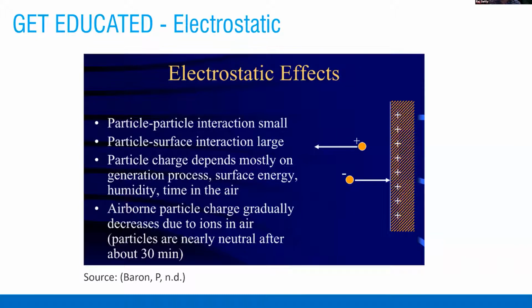Electrostatic, otherwise known as corona discharge or electrostatic precipitators, is a technology that in essence charges the particles. And you'll have a couple different ways where it charges the particles. Either the particles are positive and negative and they stick to each other, and that is called agglomeration. Or the particles have a positive charge and the filtration media has a negative and then they adhere there.